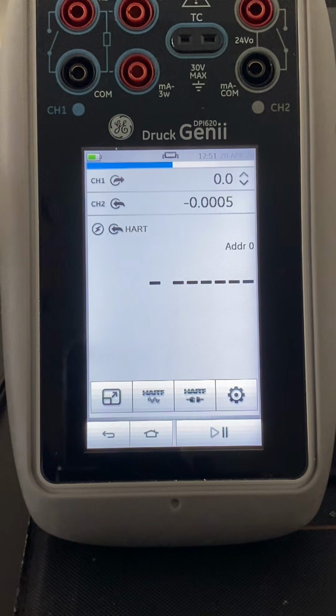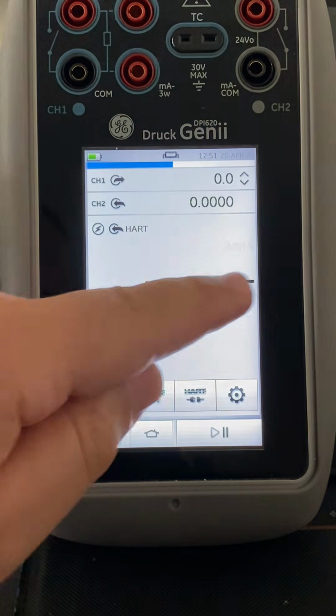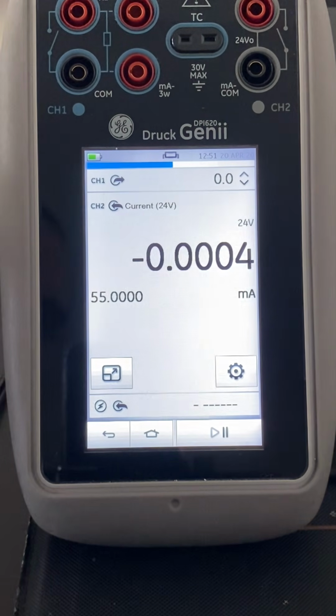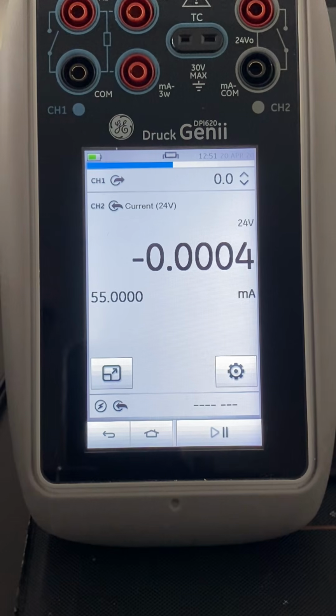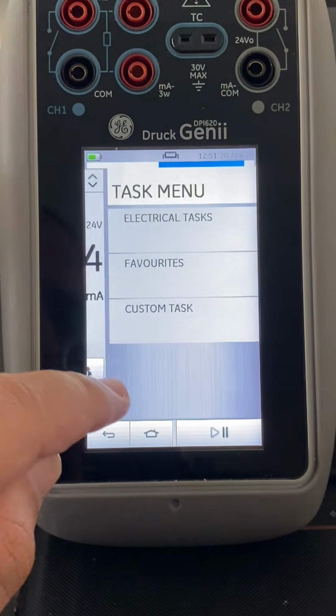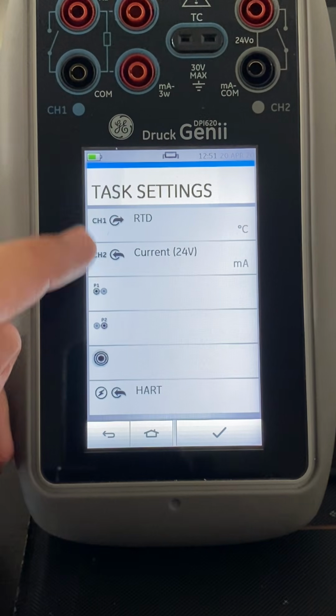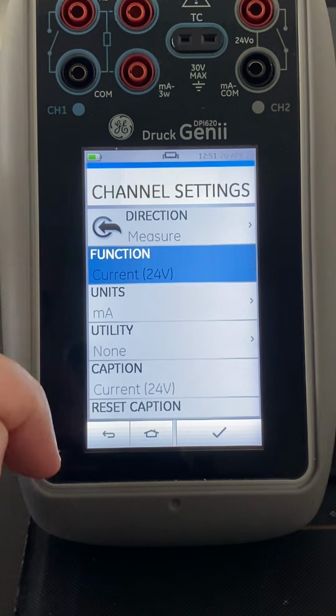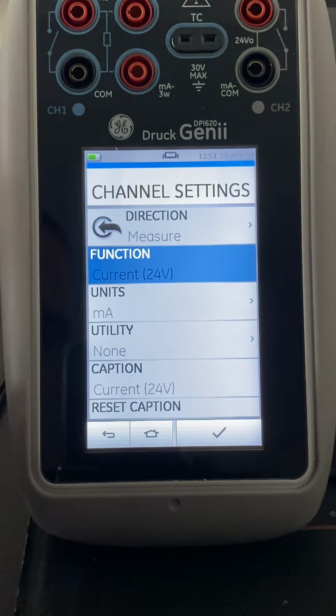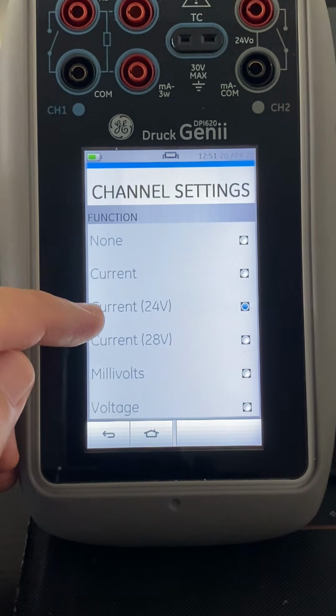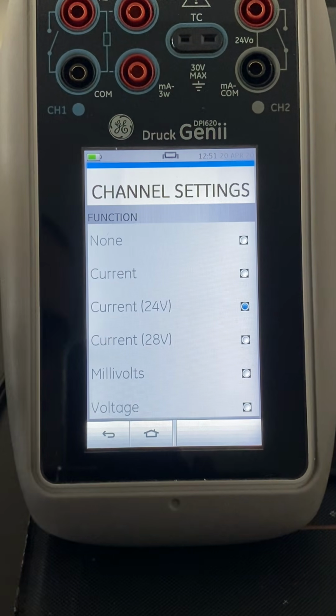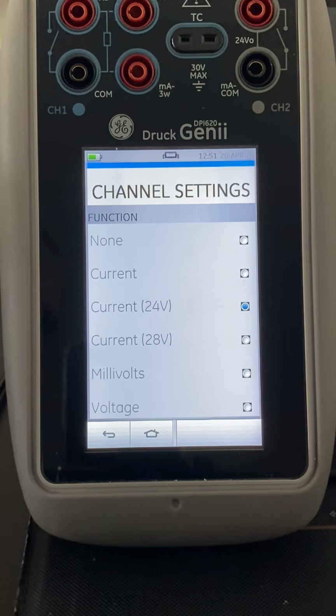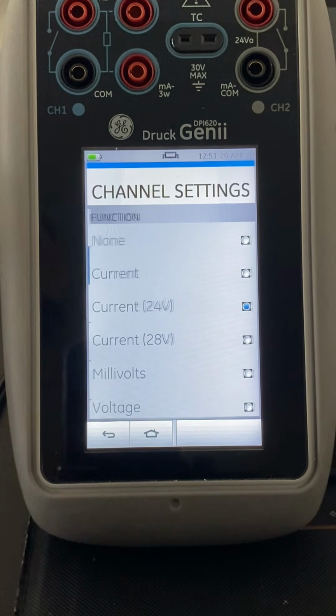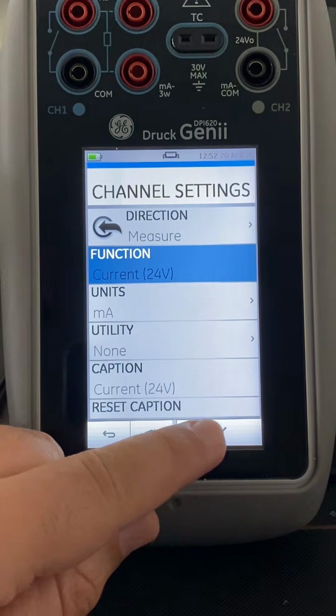Because we have a power supply in our Genii, we have an internal resistor as well. We can communicate without need for an external resistor or external power supply. The power we can get from channel 2. Here on channel 2, we wanted to measure the current and we put the current with the 24 volt, or 28, depending on the impedance of the device. Let's go with the 24 volt now because it's sufficient for our device here.